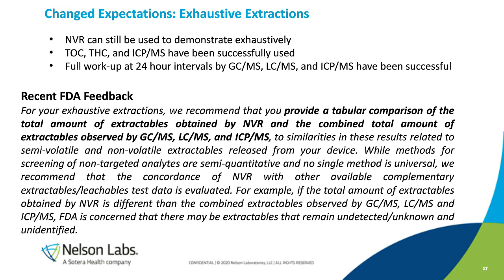It's really unlikely that the amount that you see by NVR matches what you see by GCMS, LCMS, and ICP-MS. In fact, it's almost impossible that those 2 things should really agree with each other. But if you know that this is on the FDA's radar, you can provide that comparison and explain up front why those things really shouldn't agree. So that's something that I would highly recommend.